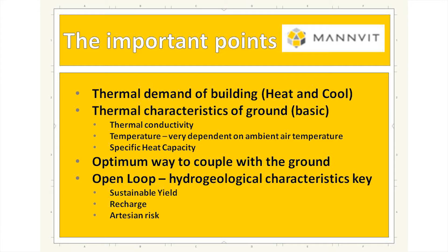Temperature depends very much on what the ambient air temperature is, but you need to know what the ground temperature is. For example, in London you're typically looking at somewhere between 12 and 15 degrees as your starting temperature at near surface, because effectively London is a heat island. If you go up to Aberdeen, you're talking about 7 or 8 degrees because it's a lot colder up there.